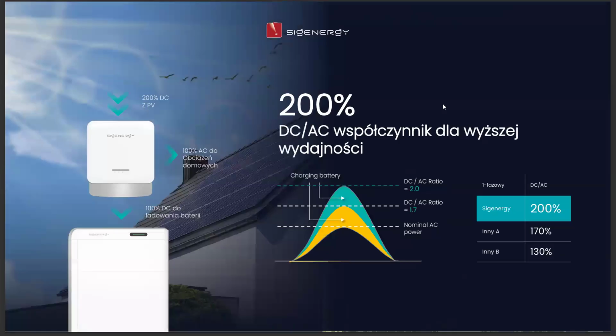Slide 16. Oversizing, more power on the roof. Our inverters support up to 200% DC oversizing. Why does this matter? On complex roof layouts, e.g., east-west, or in agrivoltaic structures, we can install PV capacity up to twice the inverter's rated power.